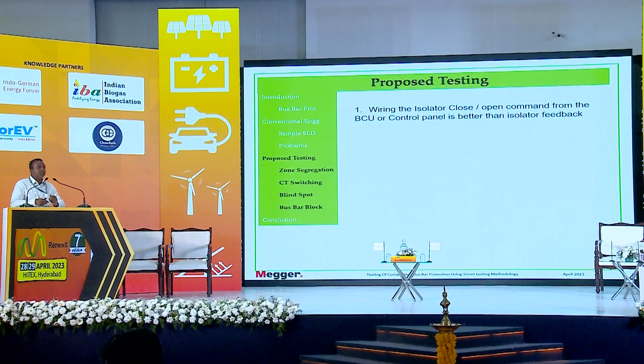The CT switching with logic security such as circuit breaker status or open pole. So the CT switching should actually be based on the circuit breaker position, when the breaker is open and when the breaker is closed. When the breaker is open, the CT can be removed from the differential calculation. When the breaker close command is issued from the SCADA or TNC switch, it can be put into service.